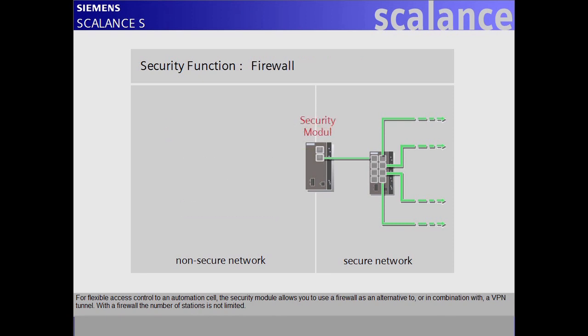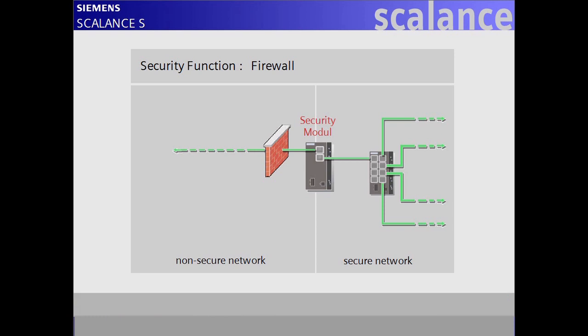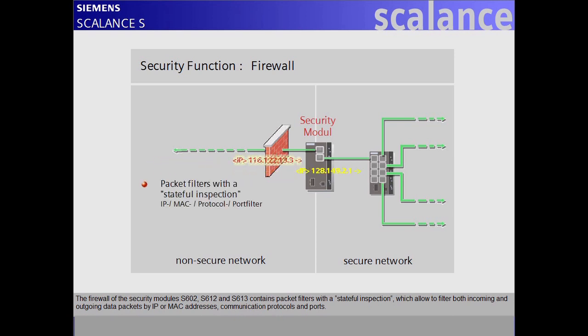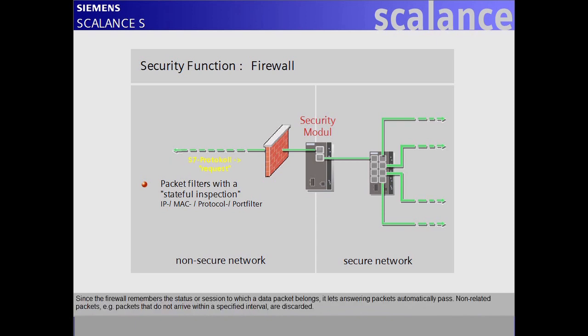For flexible access control to an automation cell, the security module allows you to use a firewall as an alternative to, or in combination with, a VPN tunnel. With a firewall, the number of stations is not limited. The firewall of the security modules S602, S612, and S613 contains packet filters with stateful inspection, which allow filtering both incoming and outgoing data packets by IP or MAC addresses, communication protocols, and ports. Since the firewall remembers the status or session to which a data packet belongs, it lets answering packets automatically pass. Non-related packets — for example, packets that do not arrive within a specified interval — are discarded.